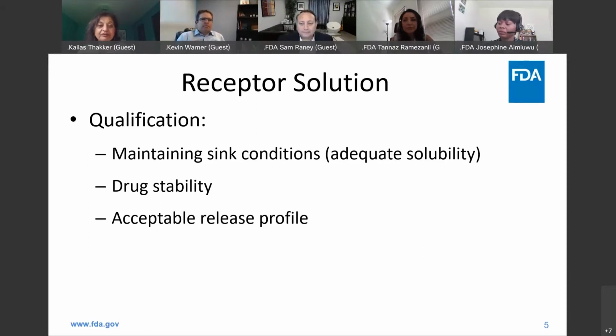I think it's perfectly okay to use hydroalcoholic solvents. You use the stronger solvents only if you don't have to worry about the environmental and safety aspects of using some of these stronger solvents, because you're using them at higher temperature. There are vapors all around. That was one of our considerations. And typically the IVRT systems are not in any kind of hood where they can vent out these solvents. So that should be considered when using strong solvents.